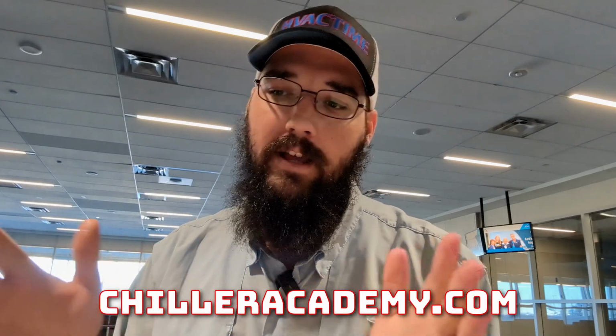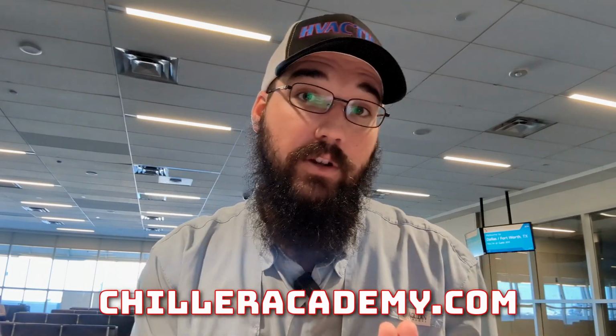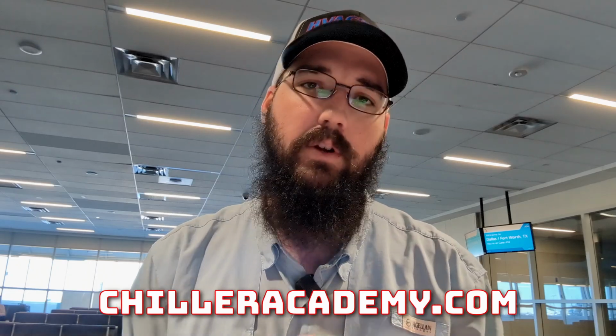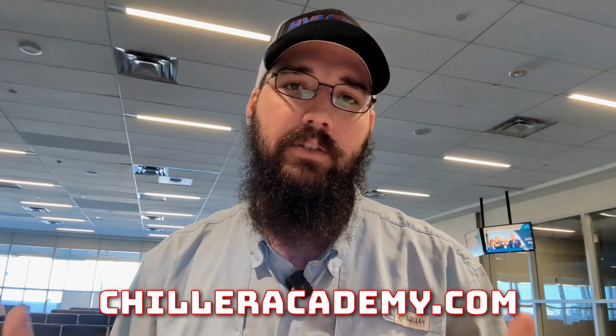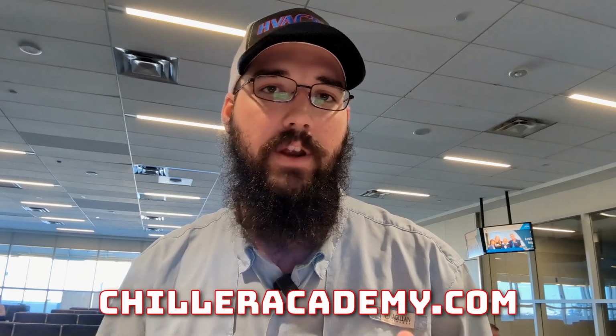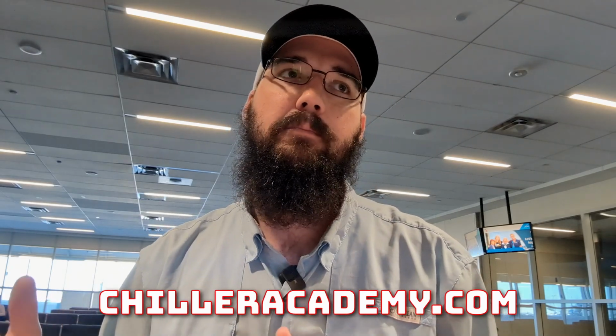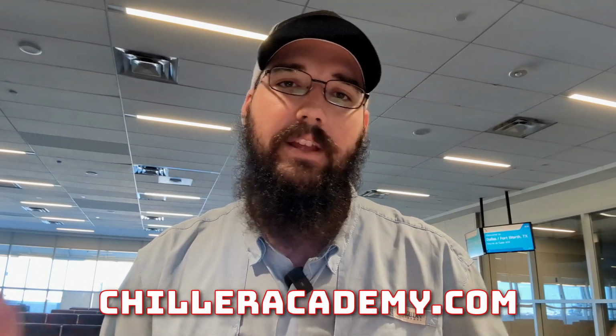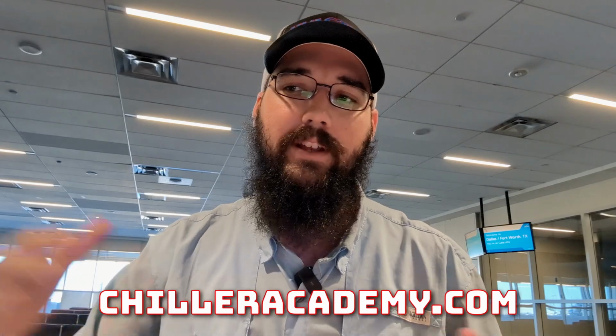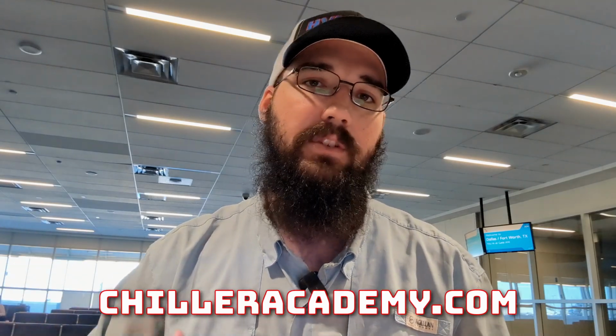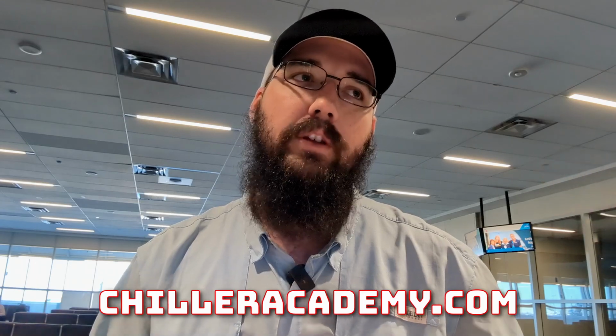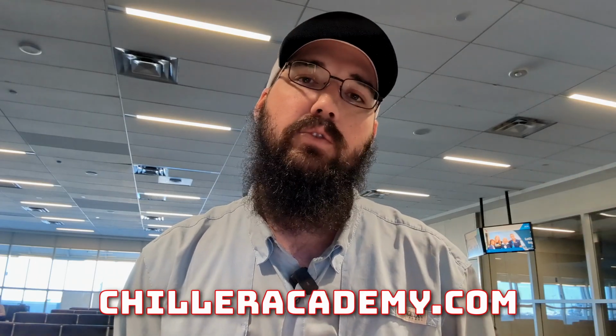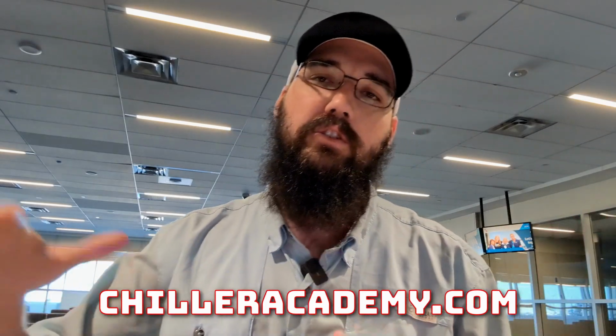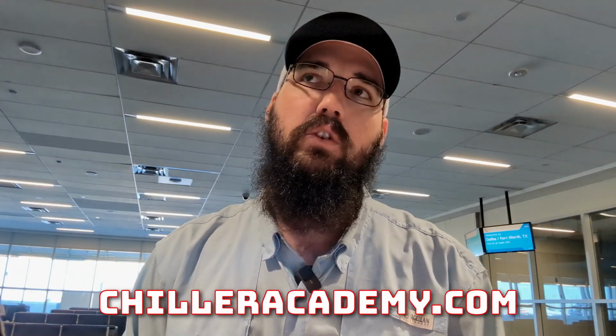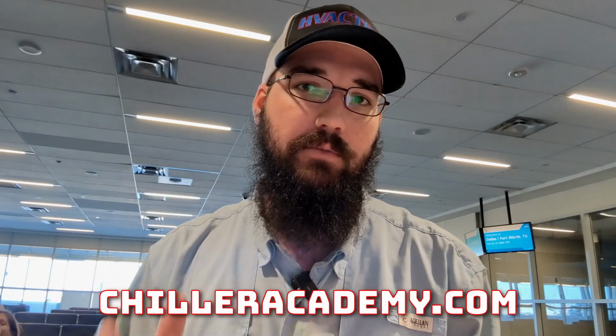Now, again, depending on how tight of a window you're trying to operate in, whether or not you're trying to do this in a really critical environment or not, more than likely you're not, especially with a question like this. So for me, 30 minutes is a very reasonable time, and it keeps anything from reacting or overreacting at that. But if you really wanted to cut that down, 10, 15 minutes would still be fairly reasonable. If we exceed our threshold by that much, then it's time to stage up or down the lag chiller. Now, you could cut that down even further if you really wanted to. You just start to risk natural fluctuations that happen anyway. So you could end up hurting your efficiency if that is your primary goal.